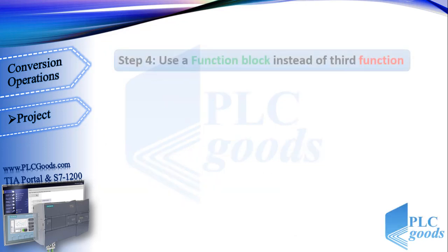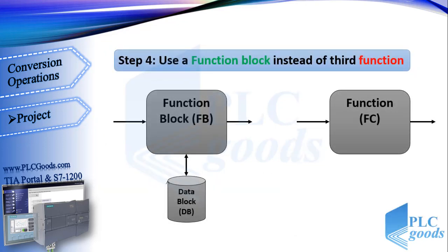Functions and function blocks both have inputs and outputs, but what is their difference? The CPU does not store anything when exiting from a function. A function block, however, has a data block and can store its data. So when the CPU starts again, the function block uses its previously stored data.